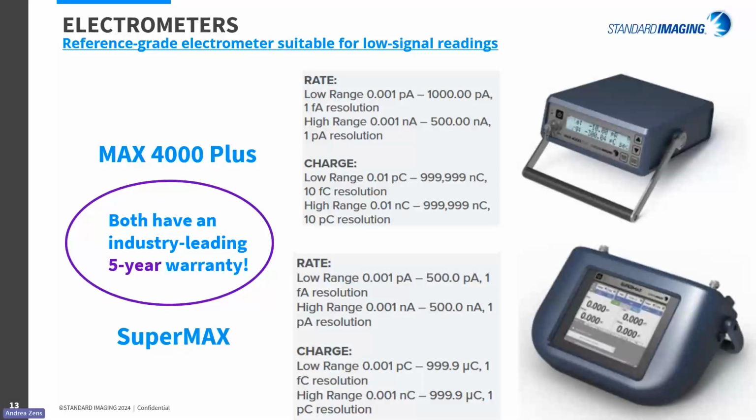As per the, again, back to MPPG 9A instrumentation guidelines, you will also need a high quality reference class electrometer that is stable and calibratable, as I also mentioned in the ion chamber considerations or detector considerations.